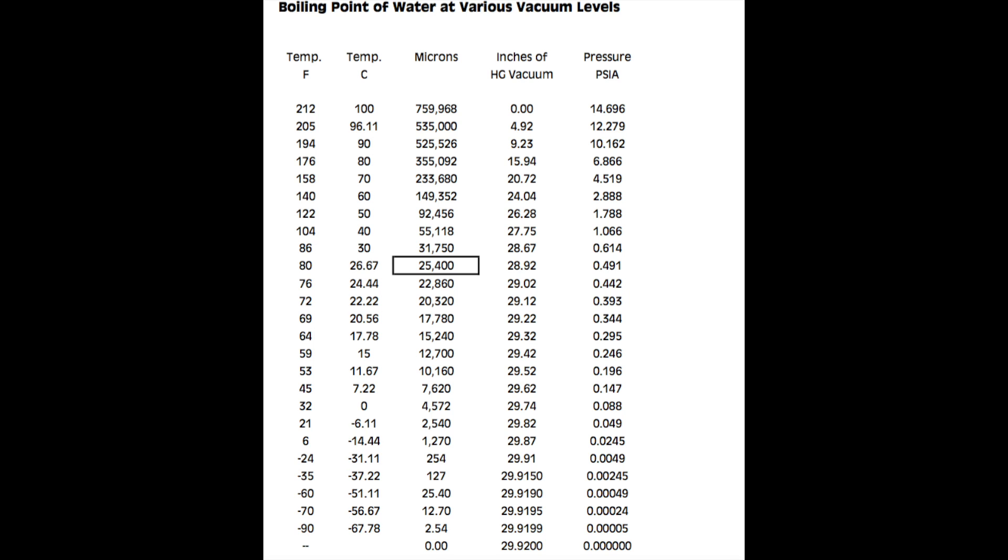It takes a lot of energy and a lot of pretty high-end equipment to get that thing down to those lower vacuum temperatures or lower vacuum pressures. So what it becomes is a very inefficient refrigerant. It takes too much power to make any sort of refrigeration happen. So in compression systems, water just doesn't work.